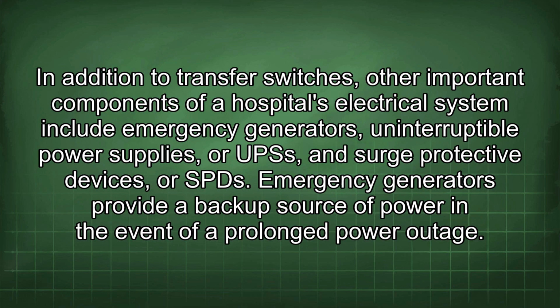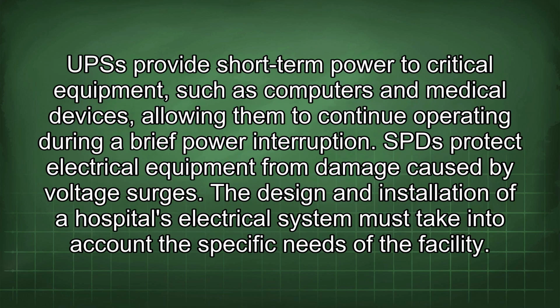In addition to transfer switches, other important components of a hospital's electrical system include emergency generators, uninterruptible power supplies, or UPSs, and surge protective devices, or SPDs. Emergency generators provide a backup source of power in the event of a prolonged power outage. UPSs provide short-term power to critical equipment such as computers and medical devices, allowing them to continue operating during a brief power interruption. SPDs protect electrical equipment from damage caused by voltage surges.